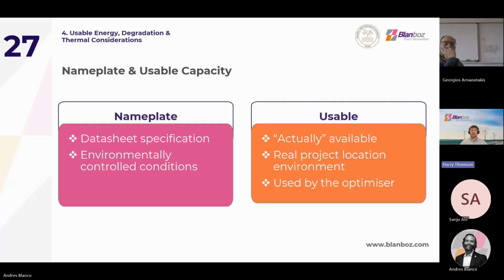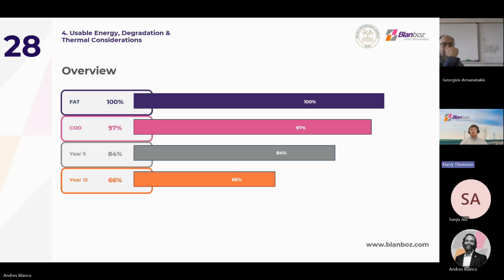Understanding the mechanics of degradation is how warranties are priced, operation and maintenance is budgeted, and how CapEx can be justified to investors, ultimately leading to the funding of a project. So this is what a BESS project's usable capacity could look like during its lifetime. At the factory acceptance test, once the equipment has been integrated, but before it has been delivered to the site, the BESS capacity is tested and recorded. This is important for assurance reasons, and it is where the BESS will be as close to nameplate capacity as possible, with it being the 100% state of health.